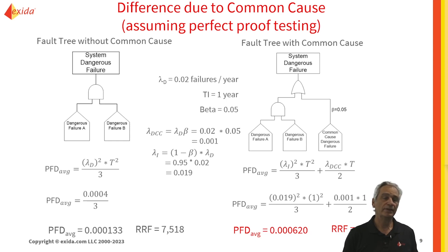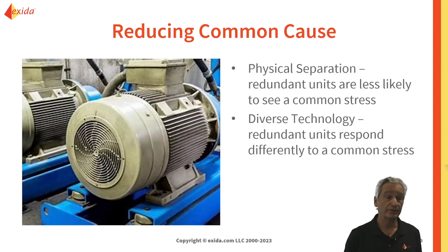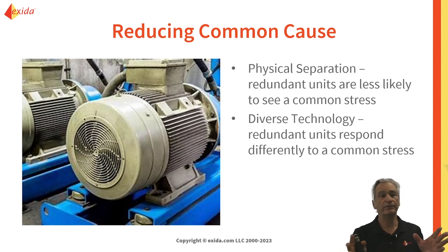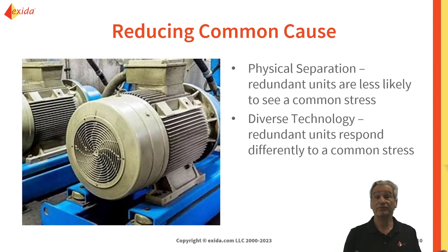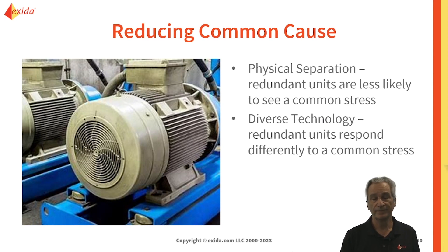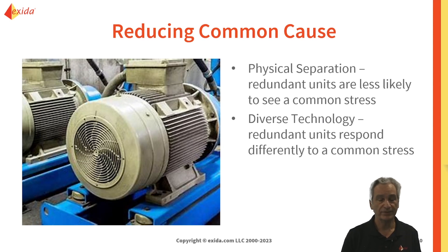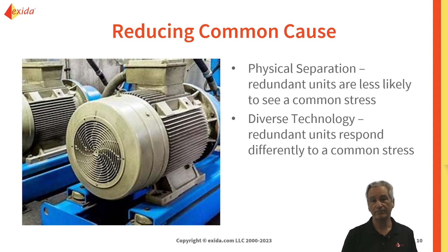What can we do in terms of some protection against common cause? Well, we can use physical separation. We can put redundant units into different cabinets and even different areas, and we can run the cabling in independent, different conduits. So they won't see as much of the common cause potential, and therefore that will help with reducing the impact.